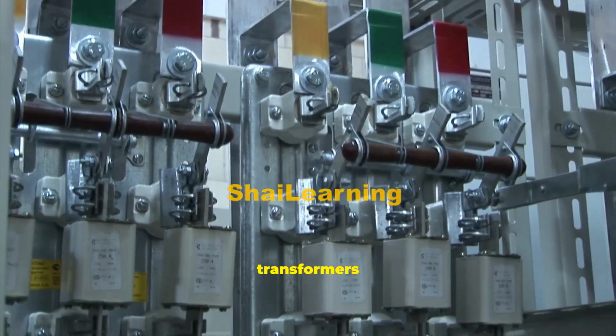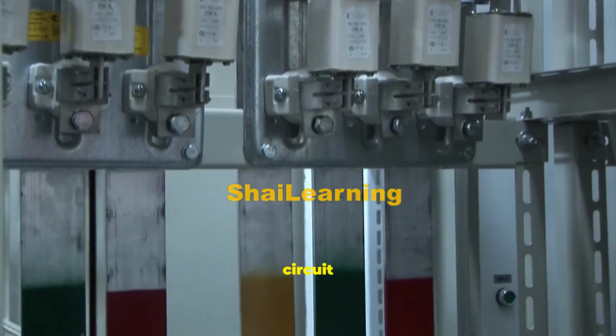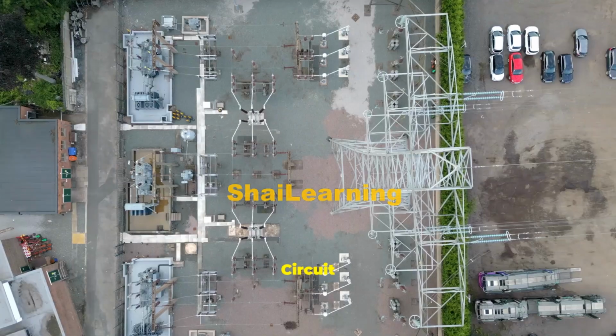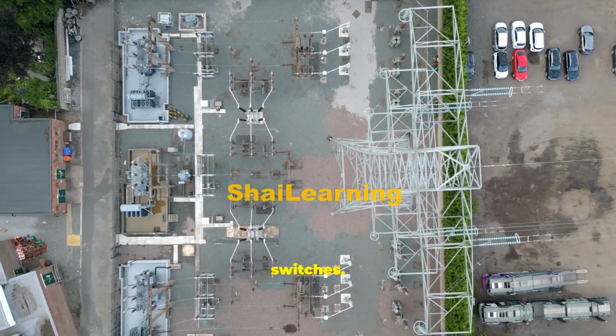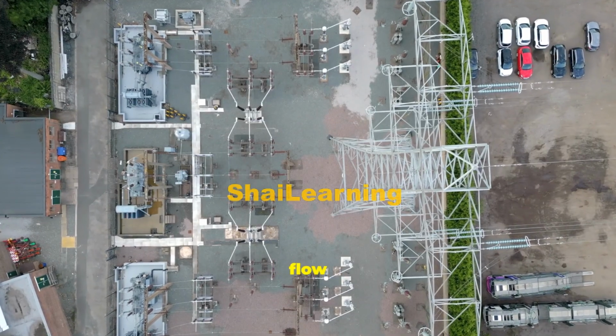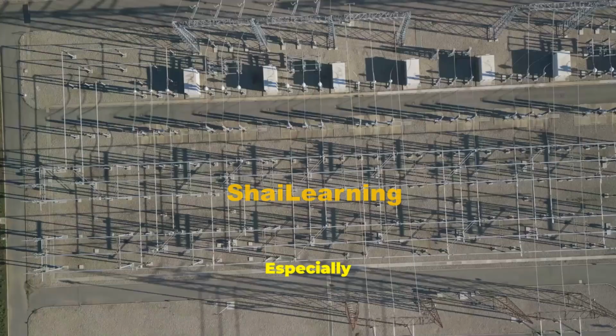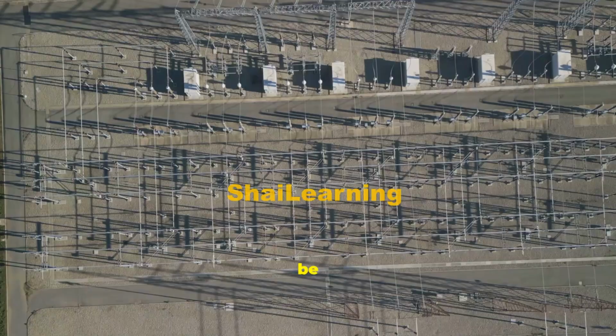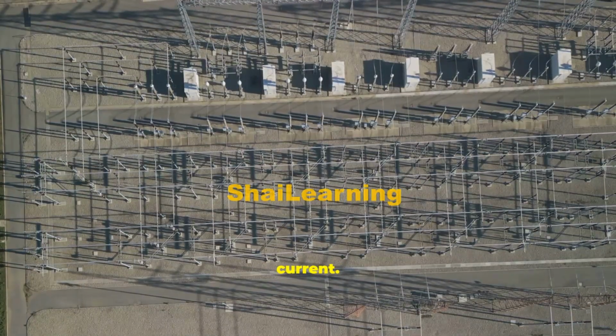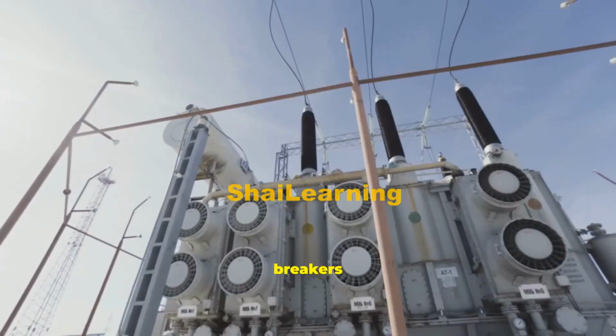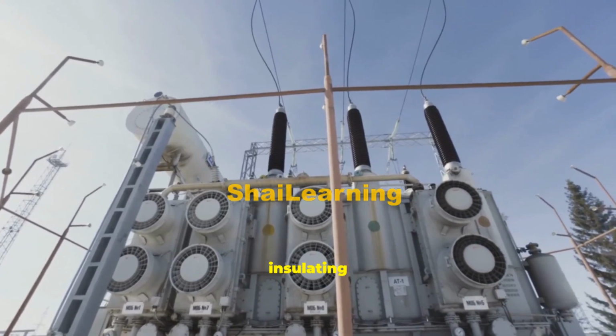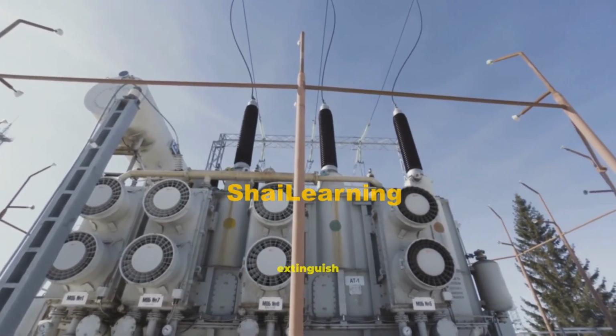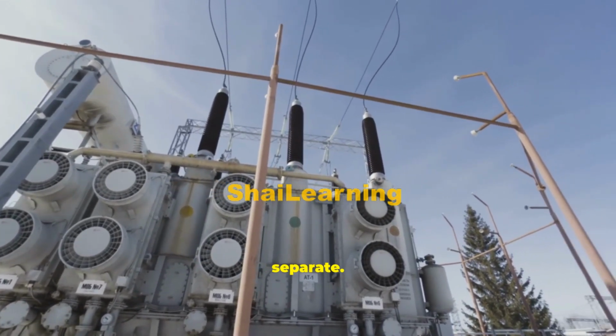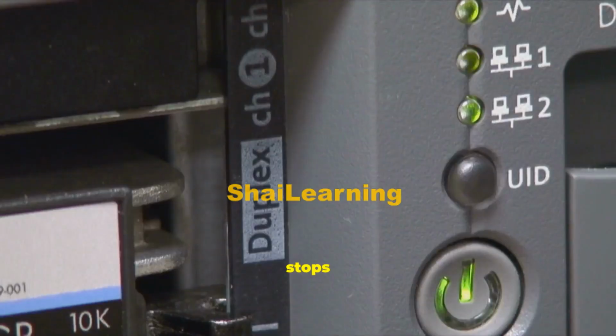To protect transformers in the grid, substations use circuit breakers. Circuit breakers are the ultimate safety switches. They interrupt the flow of electricity, especially during faults when currents can be several times the nominal circuit current. Modern breakers often use vacuum or an insulating gas like sulfur hexafluoride to extinguish the arc when contacts separate. That stops the immense fault current safely.